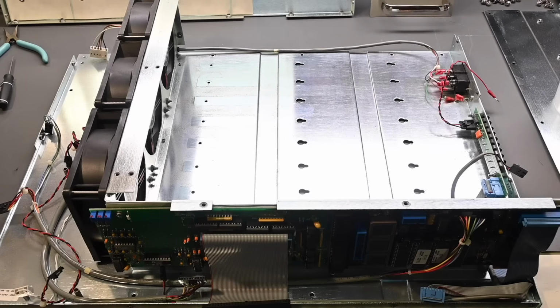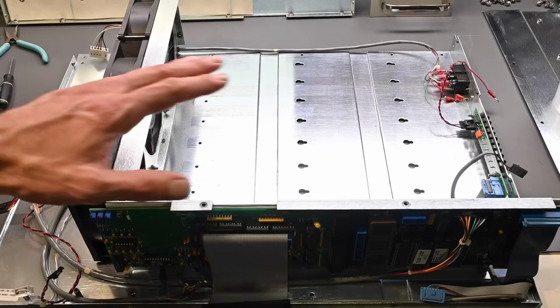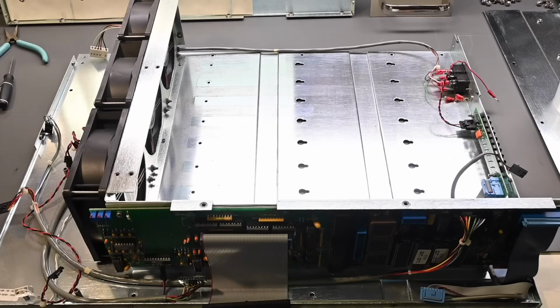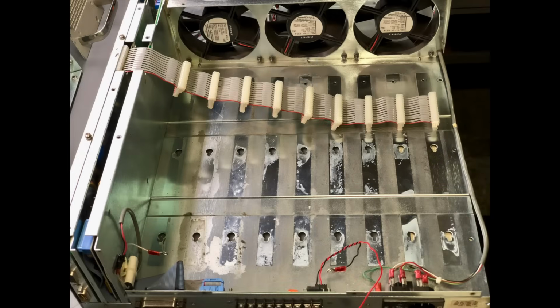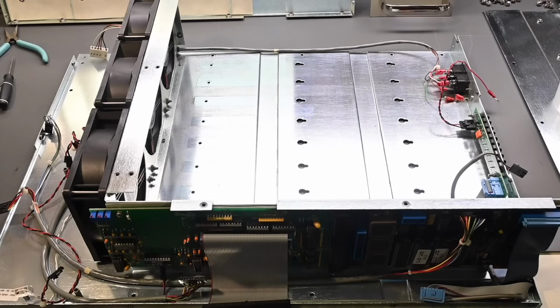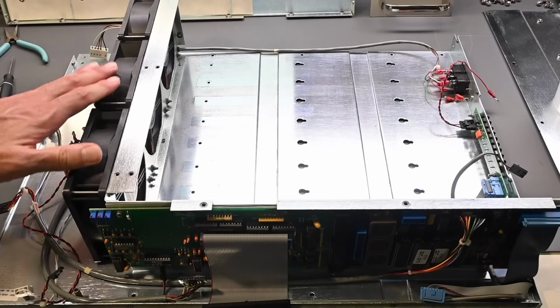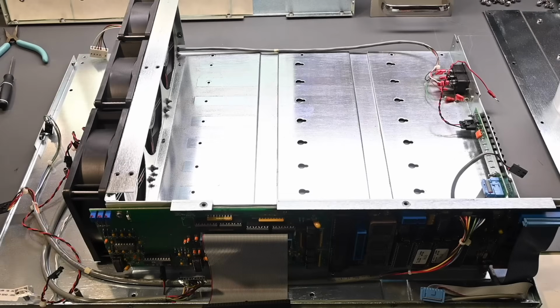In this case, the dust and lint and other things inside of the instrument really couldn't be cleaned out any other way. It completely needed to be stripped down. So the way that you see it sitting here, I've done quite a bit of cleanup on it already, and I'll put a picture up on the screen the way that it looked in this bottom part of the chassis when I got all the parts and pieces removed, and again, compare how that looked to the way it is now. You can see that I've cleaned up quite a bit. And these fans were very dusty and dirty, so those have been cleaned up already as well.